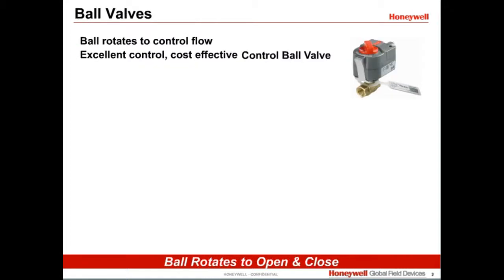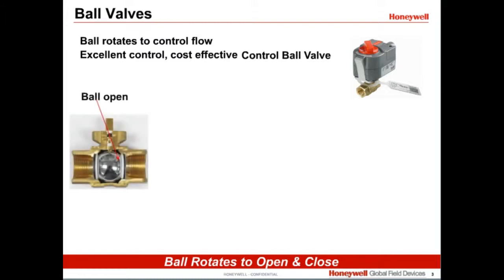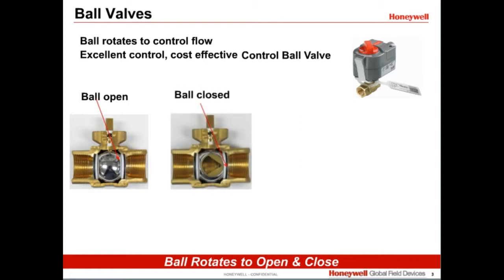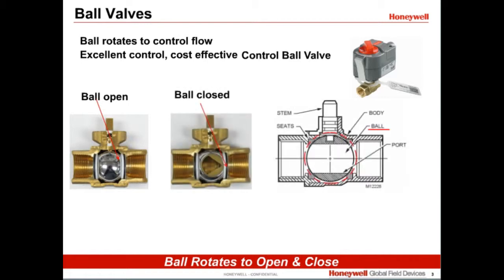Control ball valves are a unique type of rotary valve that use a ball to control flow. The ball is hollow and has two holes through the center, so that when the openings are in line with the valve ports, it will allow flow. Then the valve can be turned to restrict flow. A stem at the top of the ball protrudes through the top of the valve and allows the ball to be turned with an electric actuator.